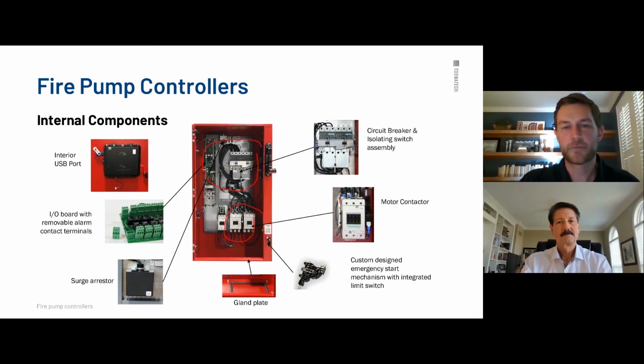Again, the preferred method for entering the control panel would be to remove the gland plate, drill your holes that are required somewhere away from the panel. You can stick it back and then run your wires up through that gland plate. That just really minimizes the amount of debris that you can get inside the control panel.